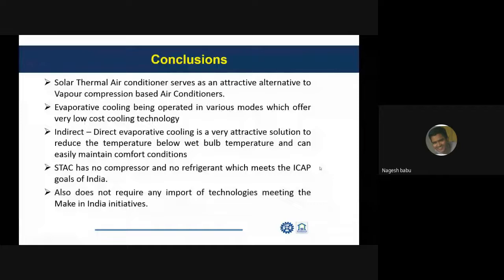So finally, conclusions. The solar thermal air conditioner serves as an attractive alternative to vapor compression based air conditioners. Evaporative cooling, being operated in various modes, offers a very low cost cooling technology. Indirect direct evaporative cooling is a very attractive solution to reduce the temperature below wet bulb temperature and can easily maintain comfort conditions. The solar thermal air conditioner has no compressor and no refrigerant, and it meets the ICAP goals, the Indian Cooling Action Plan of India, and also it does not require any import of technologies.